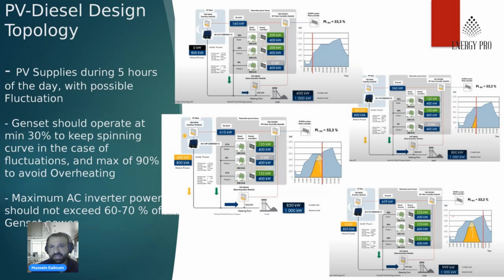Let's say at 2 a.m. in the midnight, the load is around 400 kilowatts. So there is no solar input. Then the two generators will run each at 200 kilowatt, which is around 50% of its capacity. Moving forward to, let's say, 10 a.m. in the morning, where the load is increased to 800 kilowatt, then we will have around 500 kilowatt of solar input, and the balance 300 kilowatt will be taken from the generator, each of around 150, because we need to take care that during this day solar energy, this could drop in a minute down to 100 kilowatts. So keeping two generators running, avoid loading one generator above its 90% capacity.